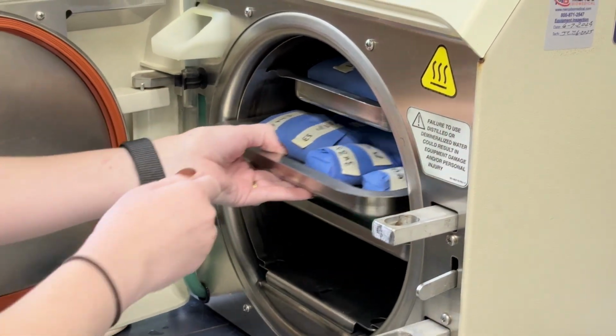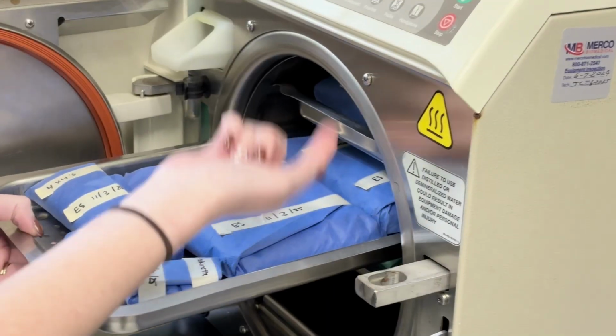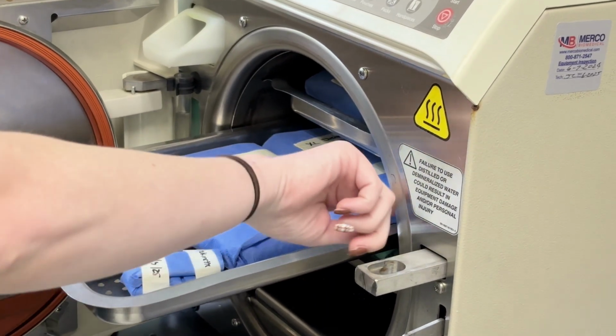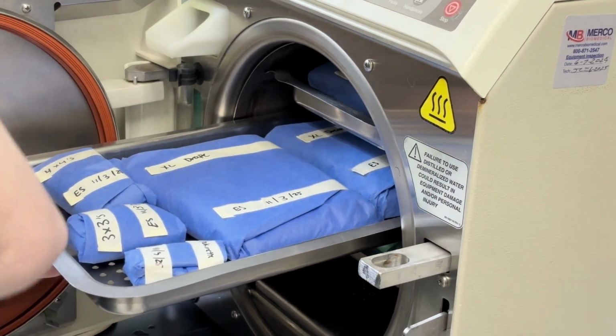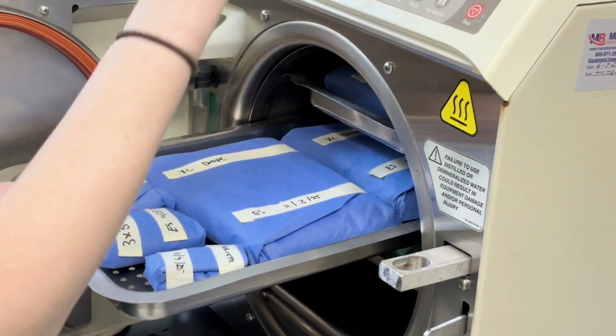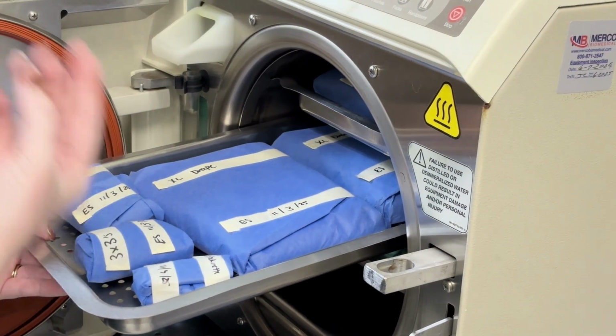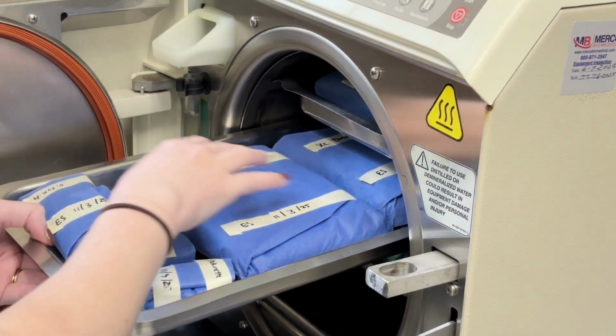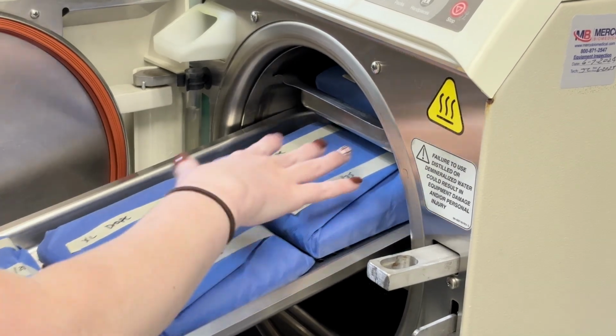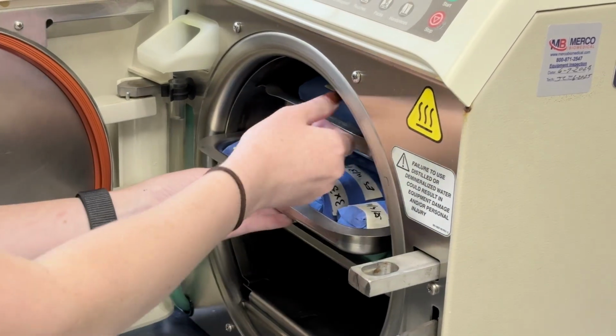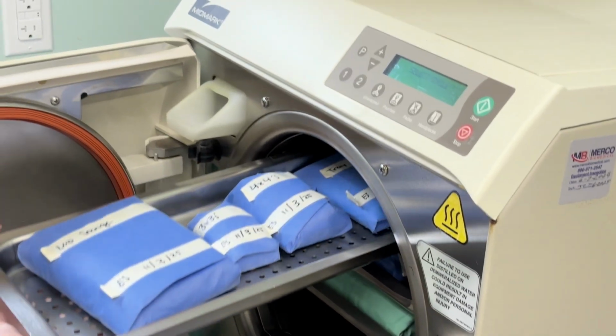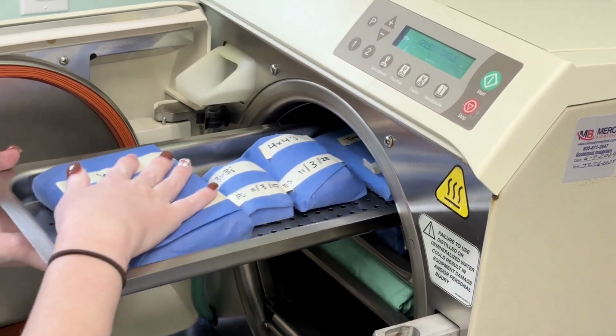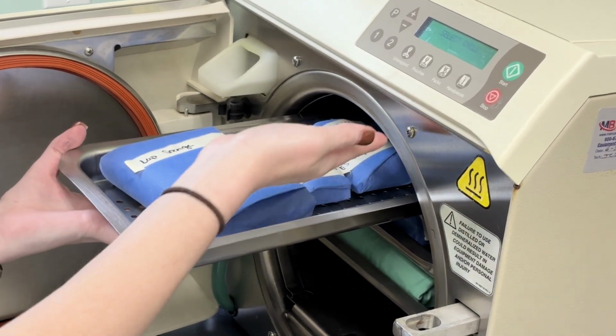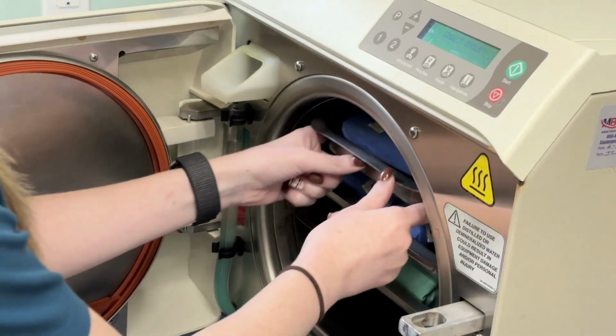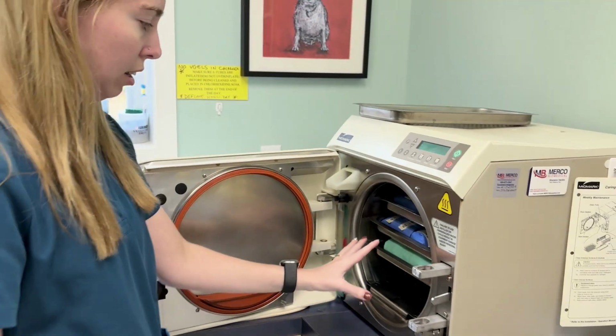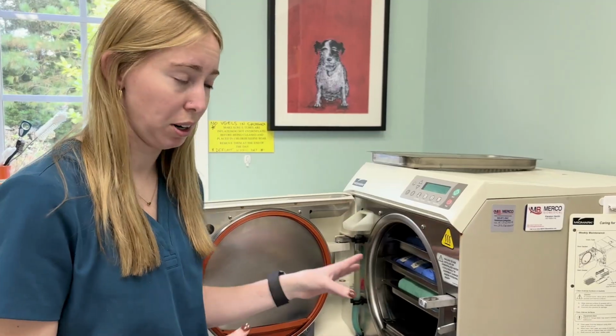So I loaded all my layers. None of them are touching the rack above them, and they're also not touching the side of the autoclave. If they are in the way of the side of the autoclave or touching on top, the steam won't get through to make everything as sterile as it can be. So all one layer, everything's here. And then we also have this last little rack up top that I added things to as well, making sure that there are small ones that fit in that area. So now that my autoclave is all packed, it is ready to run.